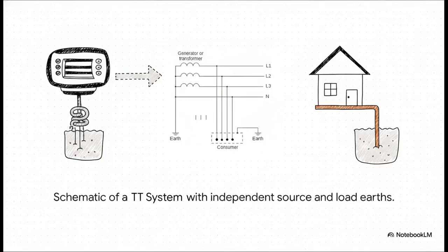Okay, let's look at a TT system. Remember our letters. That first T means the power station generator has its very own direct connection to the Earth. The second T means the consumer, so your house, has its own completely independent local Earth electrode. This is usually just a solid copper rod driven deep into the dirt outside your window. In a TT setup, the source and the load don't share a ground at all.